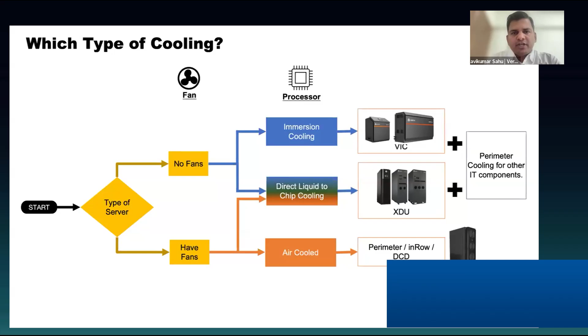So whether it's immersion cooling, the server has to have no fans. And if it's direct to chip, then some of the components may still require air cooling. So in DCLC systems, it has liquid as well as air cooling components in the servers.